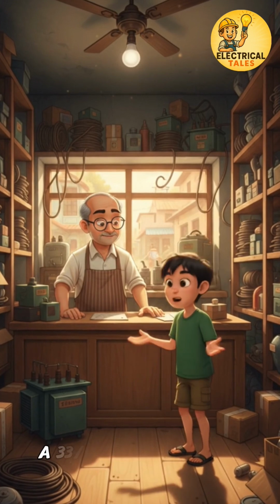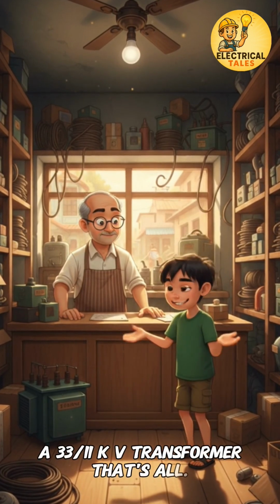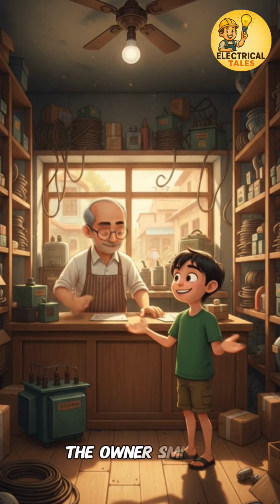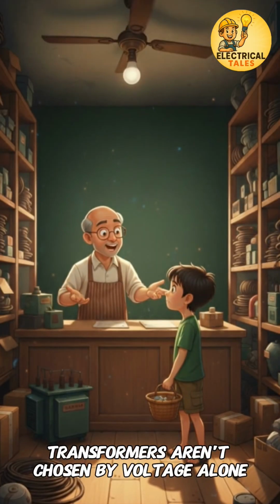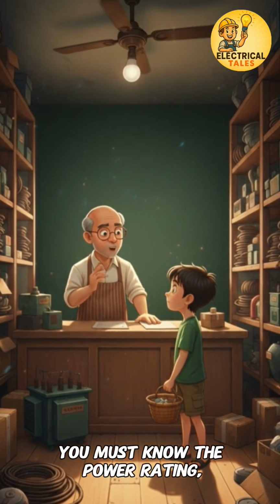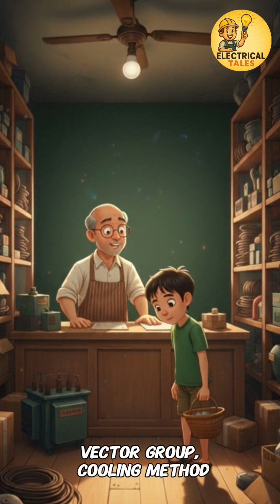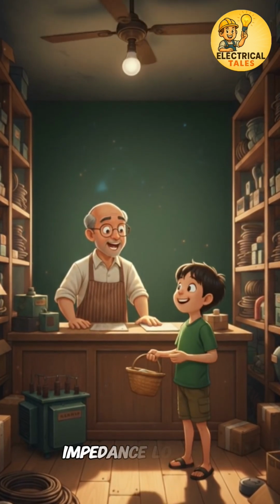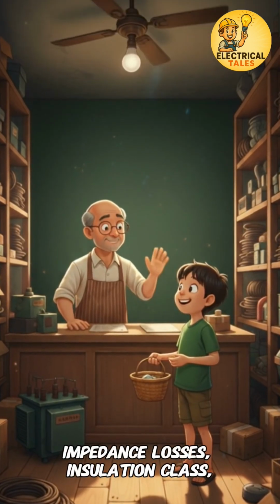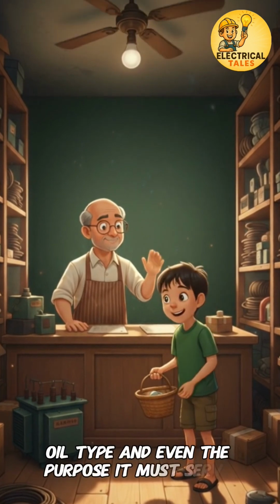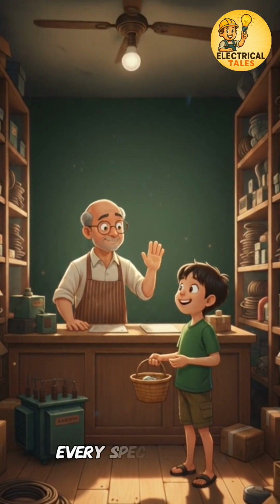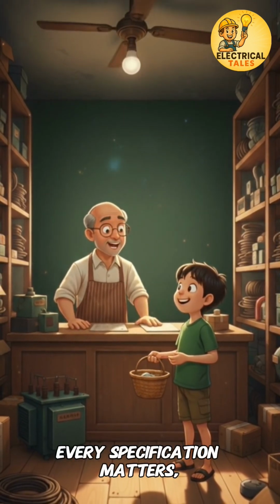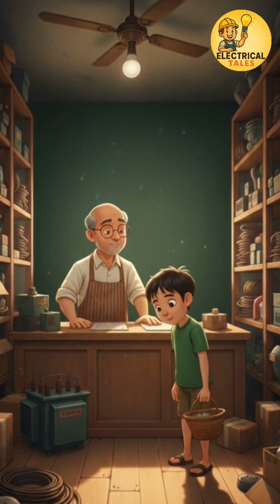Raju replied, a 33/11 kV transformer, that's all. The owner smiled patiently and said, transformers aren't chosen by voltage alone. You must know the power rating, vector group, cooling method, tap changer range, impedance, losses, insulation class, oil type, and even the purpose it must serve. Every specification matters. Raju stood puzzled.